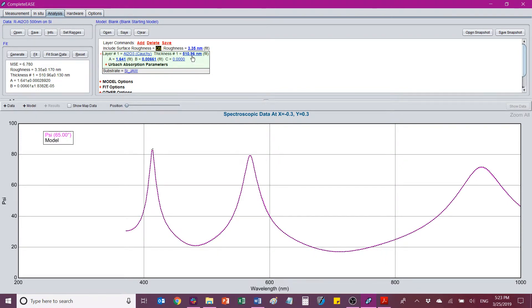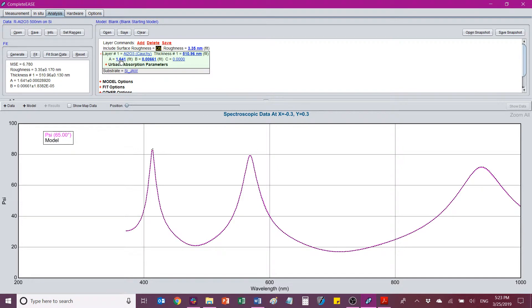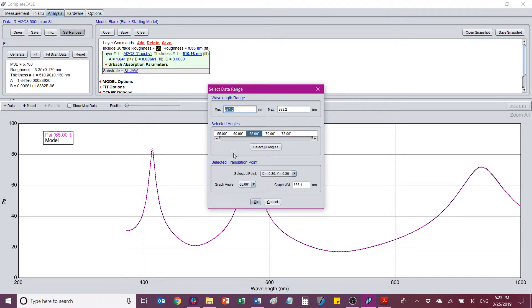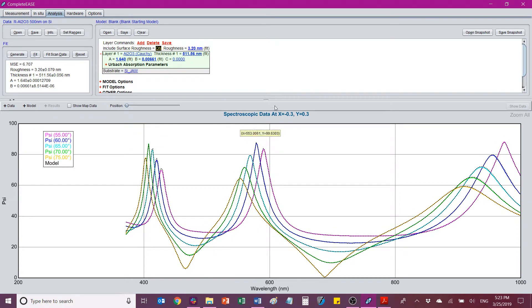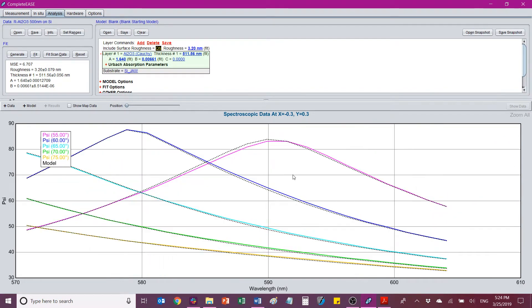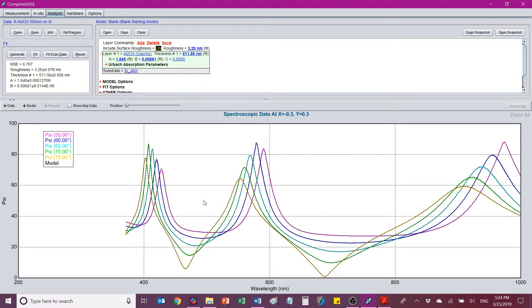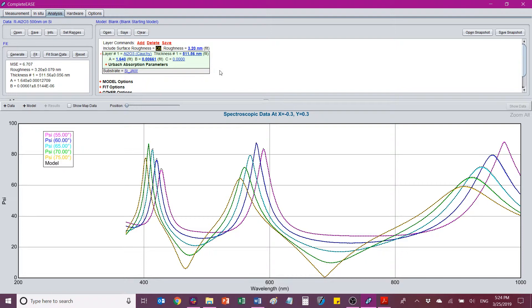So my target thickness for this film was about 500 nanometers. And it's telling me about 511 nanometers with a few nanometers of roughness. And it's telling me the properties I have are 1.64 for the index of refraction at 632 nanometers. That's roughly what this comes out to. So now I'll apply this to all of my data. I'll go back up here to set ranges. Select all angles. Okay, and then I'll just fit it to all the data. And now I have a pretty good fit. If I zoom in, I can see where the fit deviates. Okay, this is a pretty good fit. This is pretty accurate. Now there is probably a native oxide on this substrate. But if we throw that in, we'll see it really won't make much of a difference. It just complicates the model. So I'm just going to leave it like this.